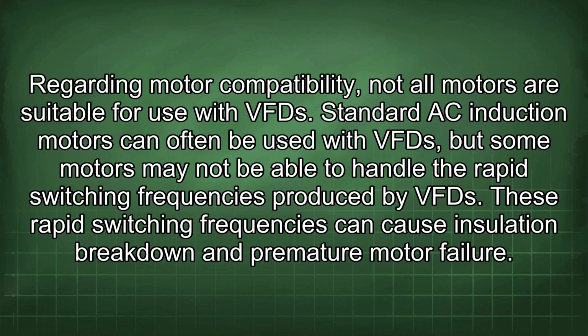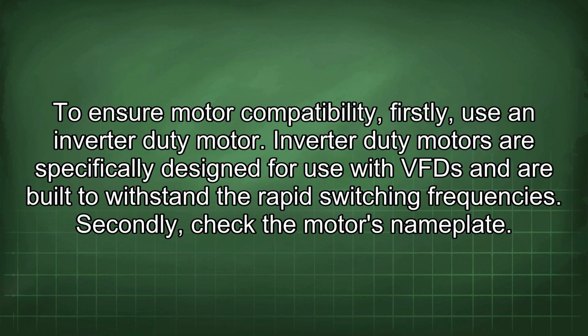Regarding motor compatibility, not all motors are suitable for use with VFD. Standard AC induction motors can often be used with VFD, but some motors may not be able to handle the rapid switching frequencies produced by VFD. These rapid switching frequencies can cause insulation breakdown and premature motor failure. To ensure motor compatibility, firstly, use an inverter duty motor. Inverter duty motors are specifically designed for use with VFD and are built to withstand the rapid switching frequencies.